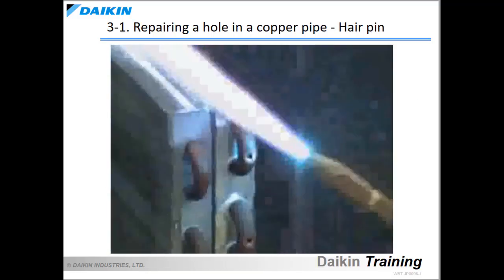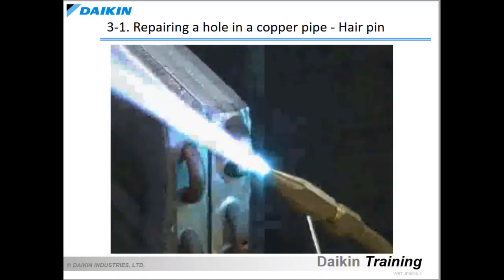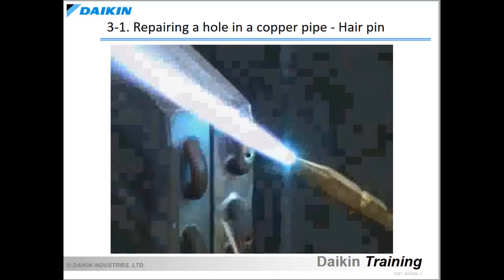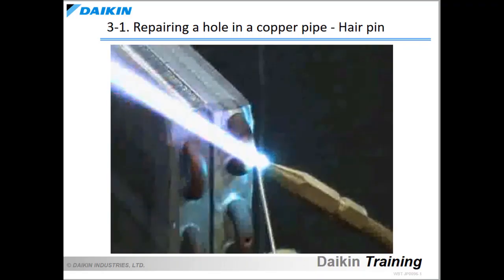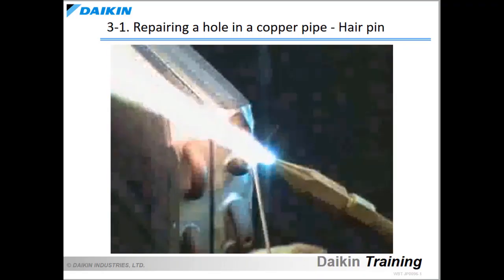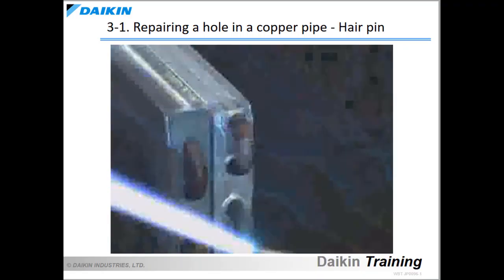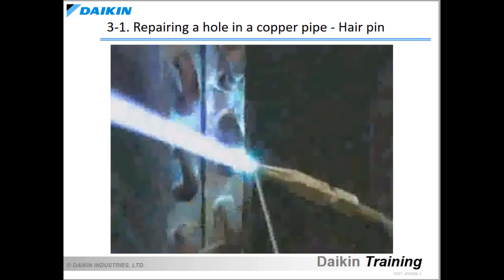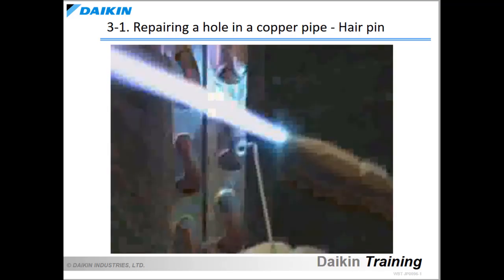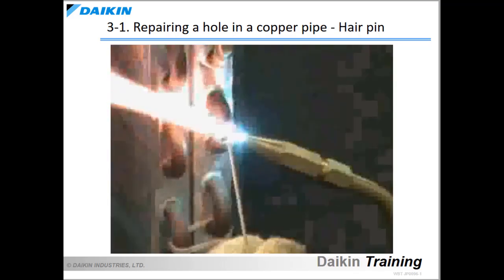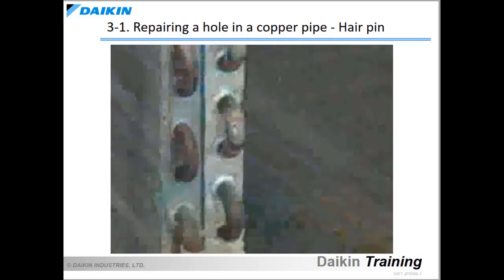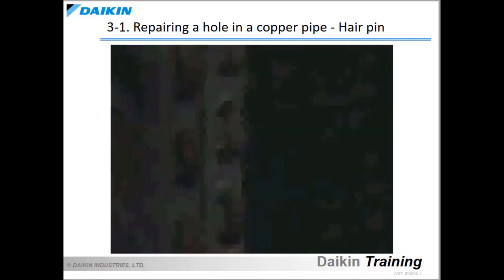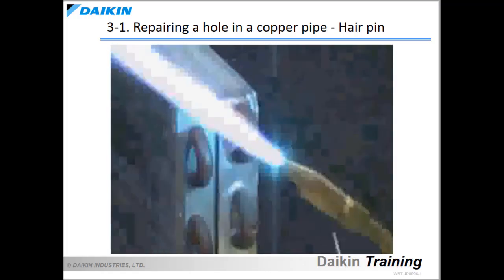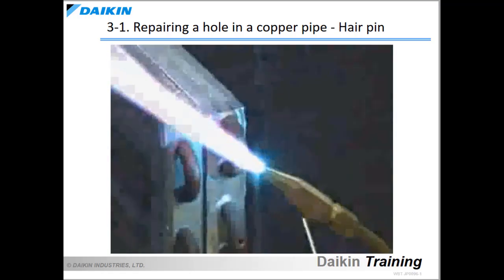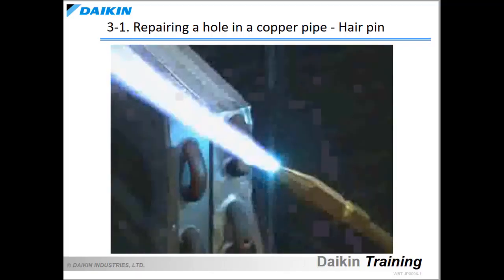Let's learn about the temporary treatment of a hole in the heat exchanger's hairpin until a new heat exchanger arrives. Use the neutral flame where the carbonizing flame overlaps the flame core. Since the hairpin is very thin, with a thickness of only 0.01 inches, it will easily melt if it comes into direct contact with the flame. Therefore, move the tip of the flame core closer to the hairpin and, as soon as the color of the hairpin changes, apply the brazing filler metal onto the hole to fill it in.